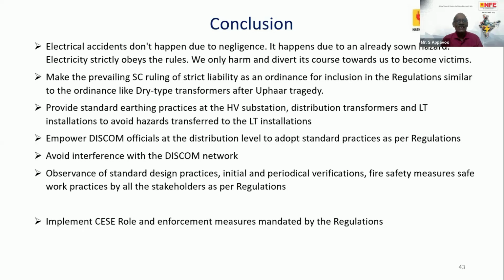So make the prevailing Supreme Court ruling of strict liability an ordinance for inclusion in the regulations, similar to the ordinance on dry type transformers after the Uphaar tragedy. Provide standard earthing practices at the HV substation, distribution substation and LT installations as well, to avoid hazards transferred to the LT installation, whether it be a consumer's equipment which is getting damaged during every load shedding or other factors where the temporary overvoltage is being transferred to the consumer installation.